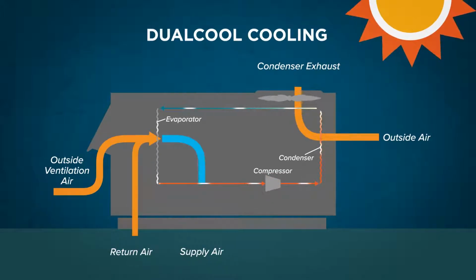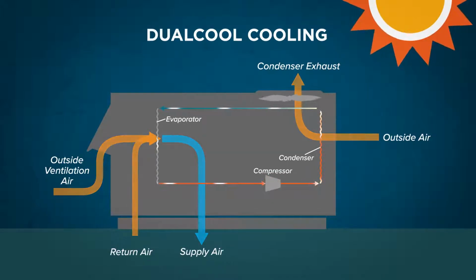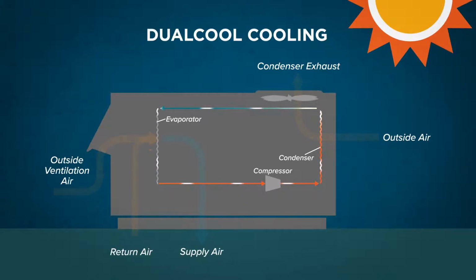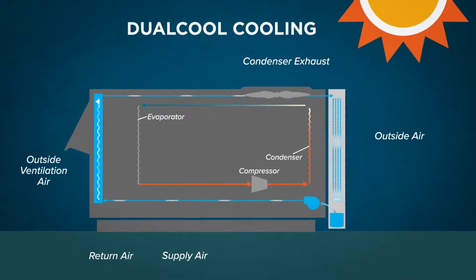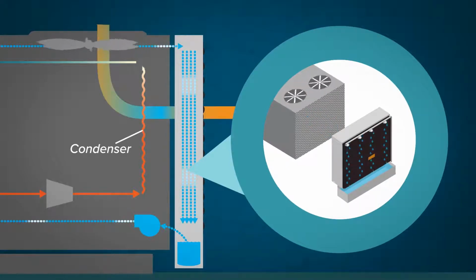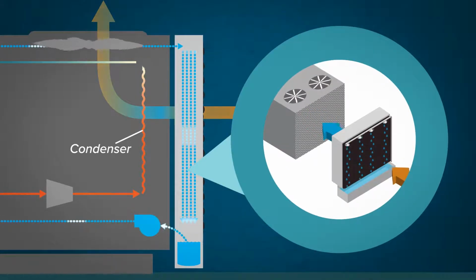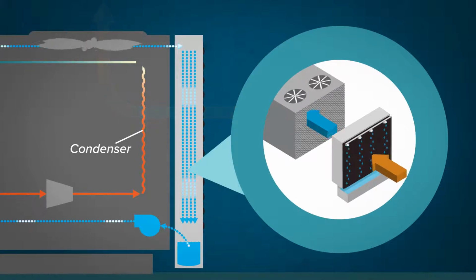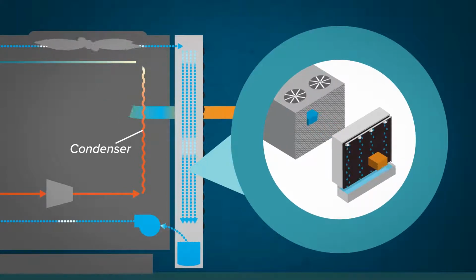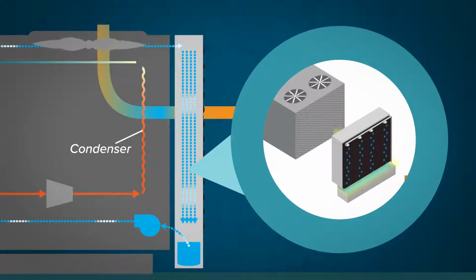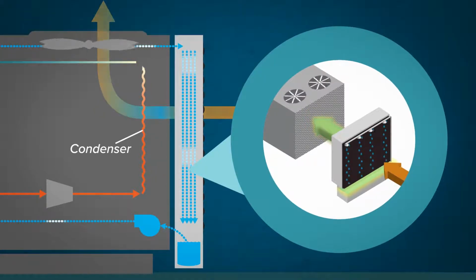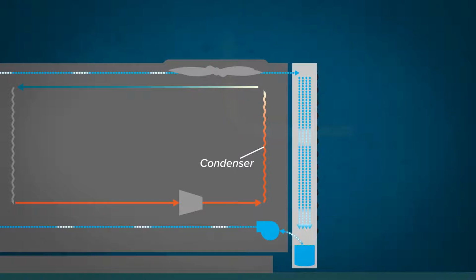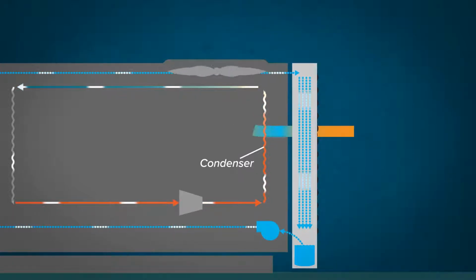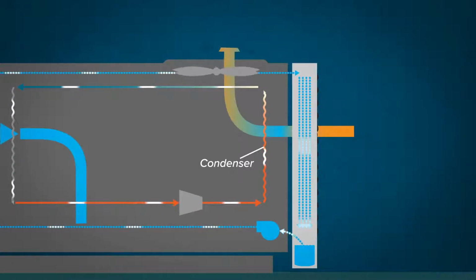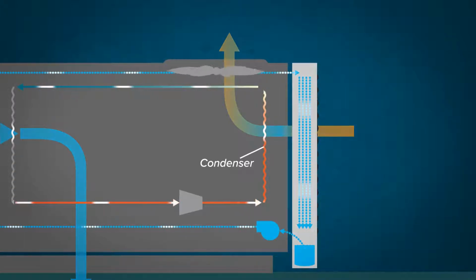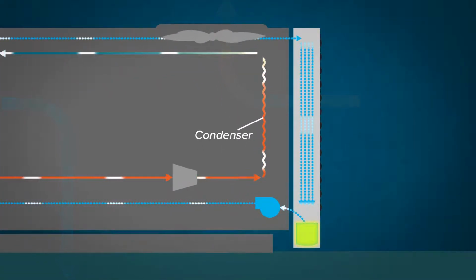One of the ways DualCool saves energy is by cooling the air around the condenser, making it easier to reject the heat to the outside. DualCool cools the air around the condenser by pumping water over a rigid evaporative media. As the warm outdoor air passes through the media, the heat of the airstream evaporates the water into the air, cooling both the air and water exiting the media. The chilled air then arrives at the condenser coil, allowing the air conditioner to operate more efficiently, as if the outdoor temperature were lower. In the process, DualCool also generates cold water.